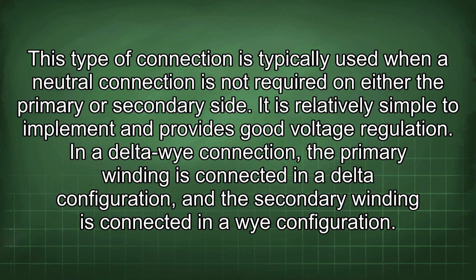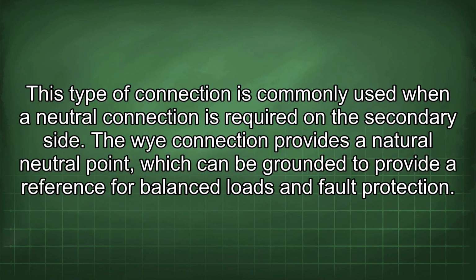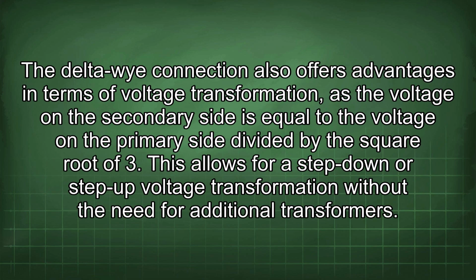In a delta-Y connection, the primary winding is connected in a delta configuration and the secondary winding is connected in a Y configuration. This type of connection is commonly used when a neutral connection is required on the secondary side. The Y connection provides a natural neutral point which can be grounded to provide a reference for balanced loads and fault protection. The delta-Y connection also offers advantages in terms of voltage transformation, as the voltage on the secondary side is equal to the voltage on the primary side divided by the square root of 3. This allows for a step-down or step-up voltage transformation without the need for additional transformers.